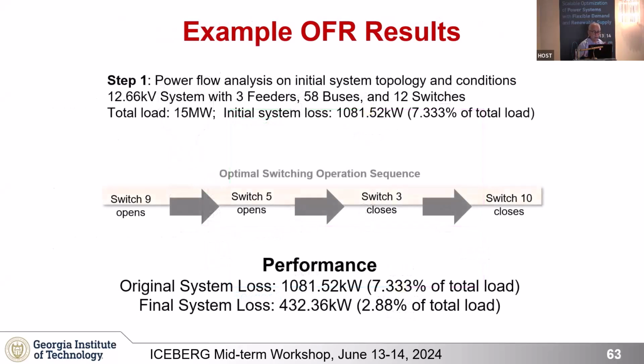Here is one solution of the optimization. Notice this is pretty much a solution for an actual feeder. Without reconfiguration, we have losses of about 1 megawatt; with reconfiguration, we drop to 0.4 megawatts. So that's a big change for that feeder.